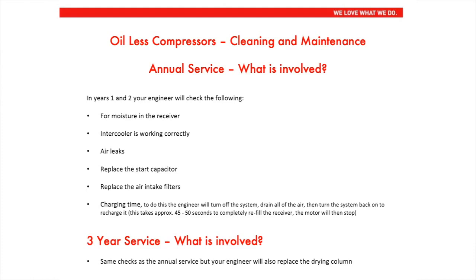Charging time. To do this, the engineer will turn off the system, drain all of the air, then turn the system back on to recharge it. This takes approximately 45 to 50 seconds to completely refill the receiver. The motor will then stop. A 3-year service, what is involved? Same checks as the annual service, but your engineer will also replace the drying column.